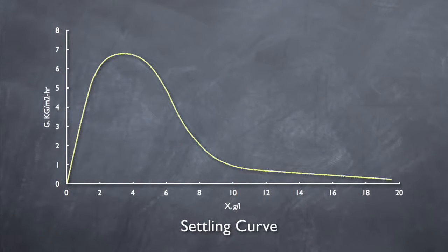The first component is the settling curve. This curve is developed by performing velocity settling tests at various concentrations of mixed liquor on site. However, empirical equations based on the sludge volume index, SVI, have been developed and are plenty accurate for using and deriving this curve.